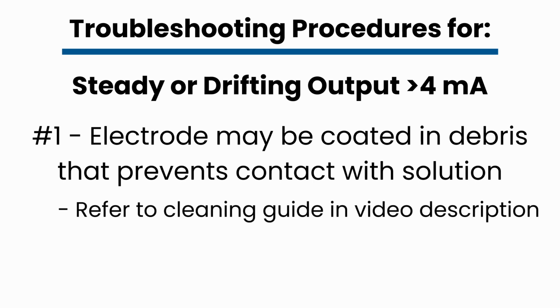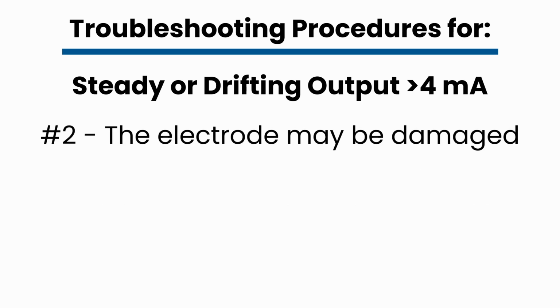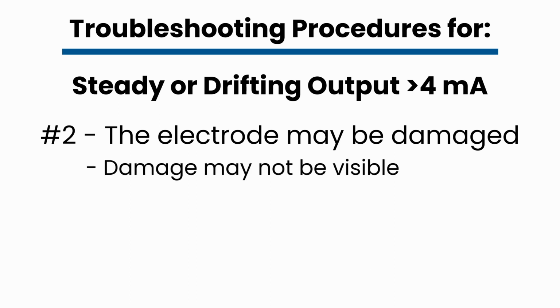The second possibility is that the electrode may be damaged. This is extremely unlikely for conductivity sensors, but does happen if the glass bulb of pH or ORP electrodes gets cracked, or if the membrane tears on dissolved oxygen electrodes. Please note that this damage may be small and difficult to see, so it's tough to identify.